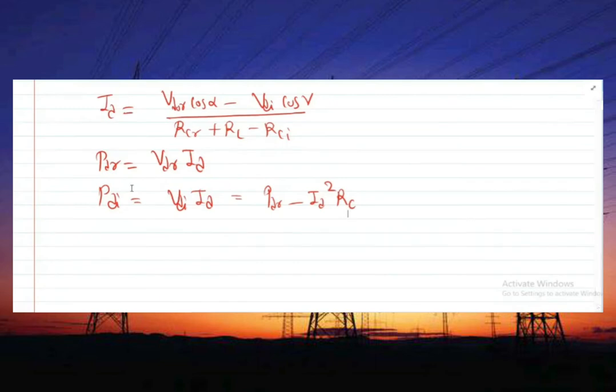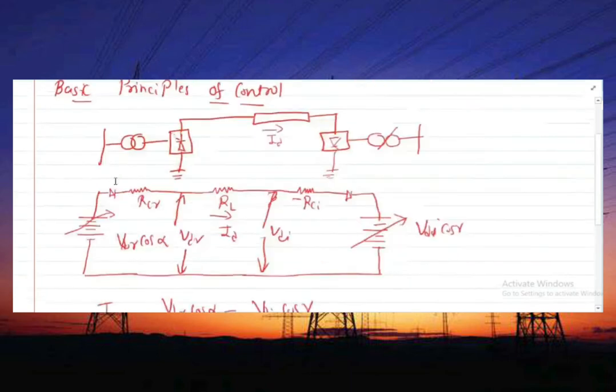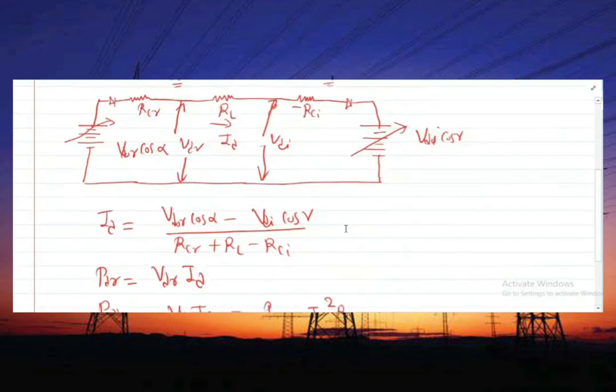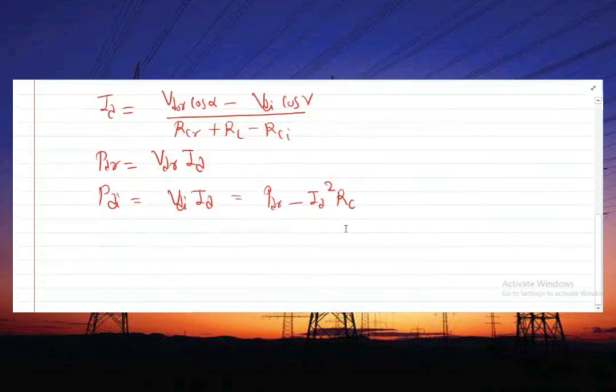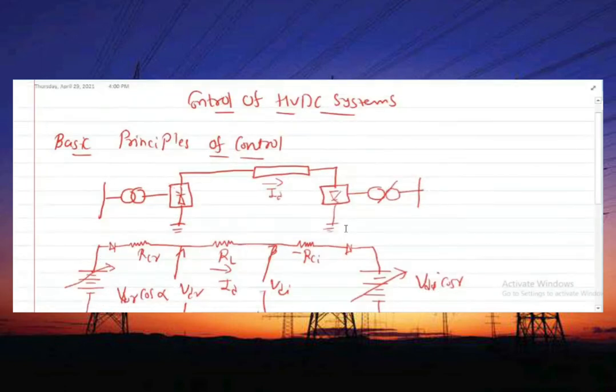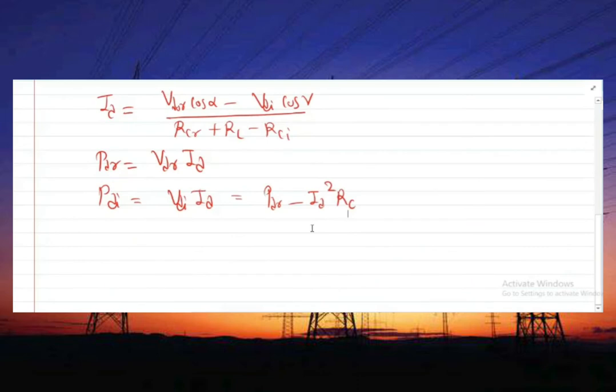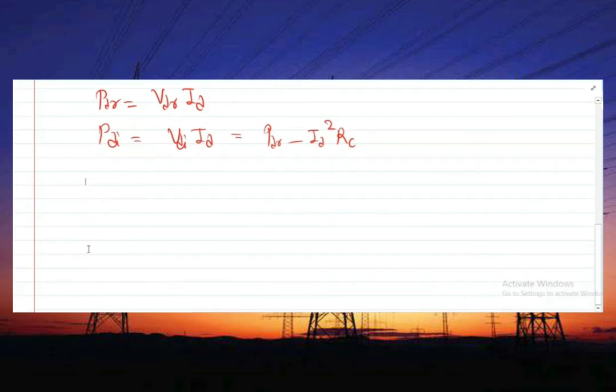The gate control which is very fast, 1-10 milliseconds, and the tap changing which is slow, 5-6 seconds per step, are used in a complementing manner. The gate control is used initially for rapid action followed by tap changing to restore the converter quantities to the normal range. Power reversal is obtained by reversing the polarity of the direct voltage. Now, how can you select the controls? Some considerations influence the selection of the control characteristics.